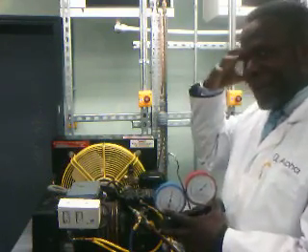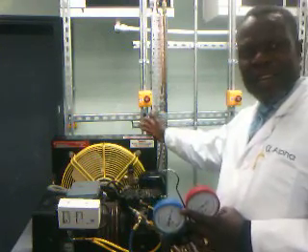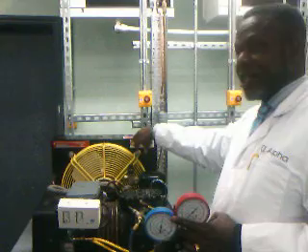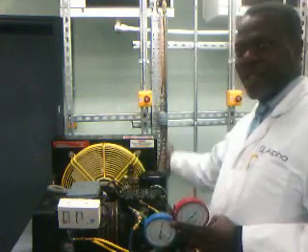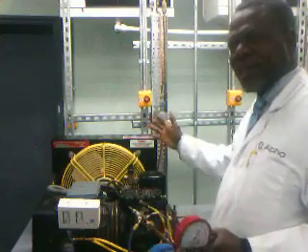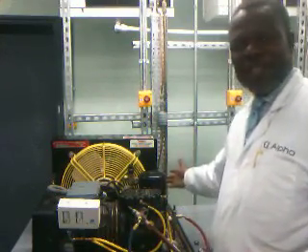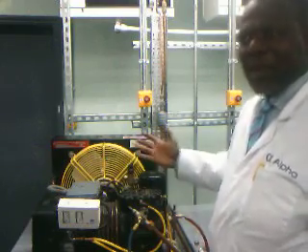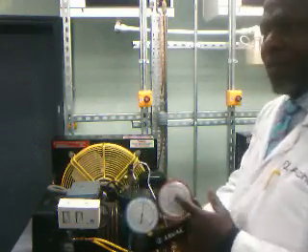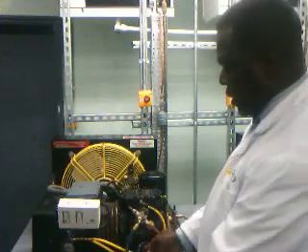Sometimes it baffles people when you say the reading here is the condensing temperature, and that is why people dispute the fact that there's no change in temperature. Some people say, no, it's not possible. The fan is blowing heat out of the refrigerant, and now you are saying temperature is not going down. They don't believe it. But that is how it is. You can always get it from here when you compare. Any more questions on subcooling?